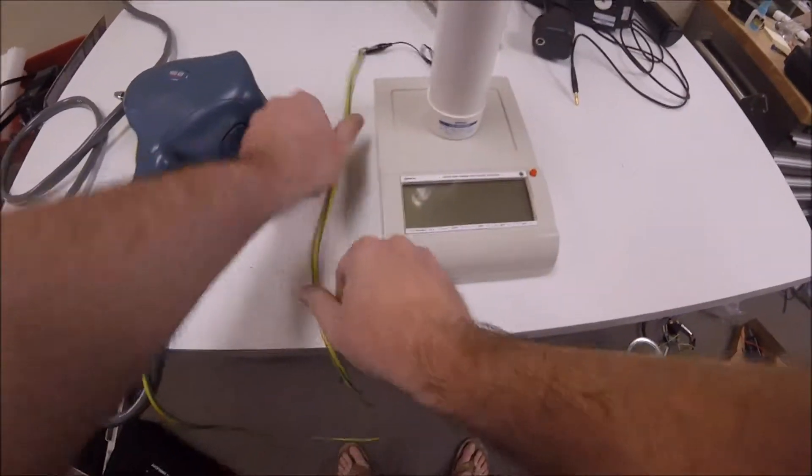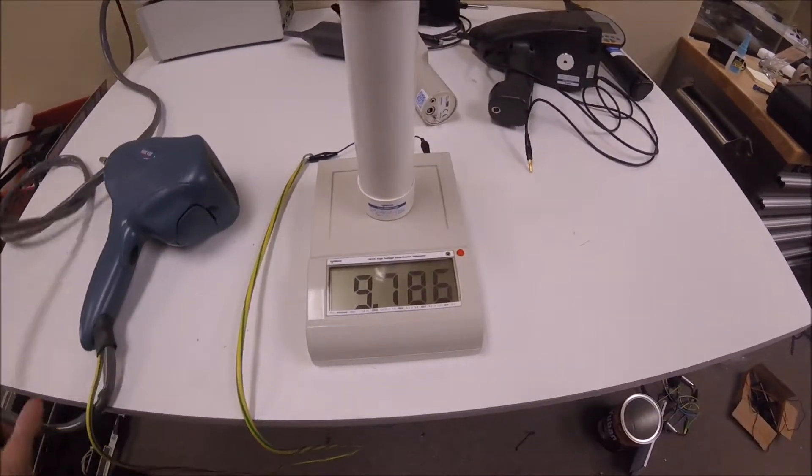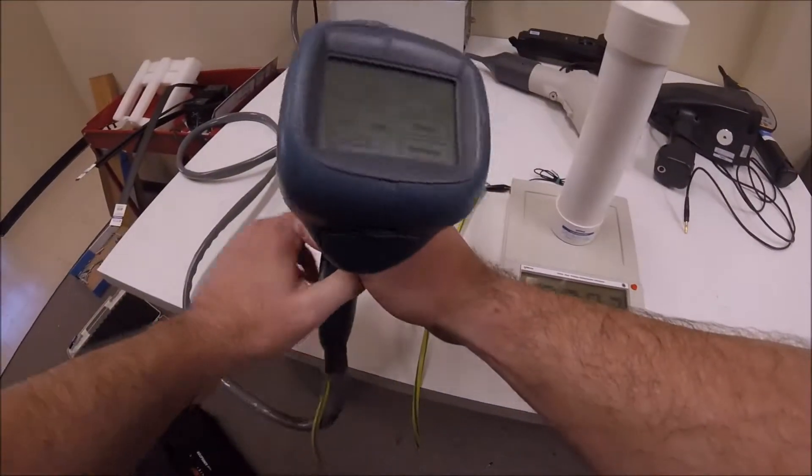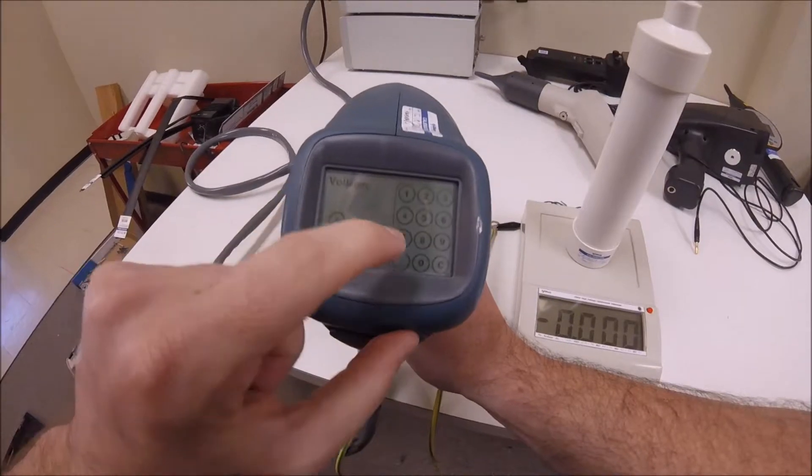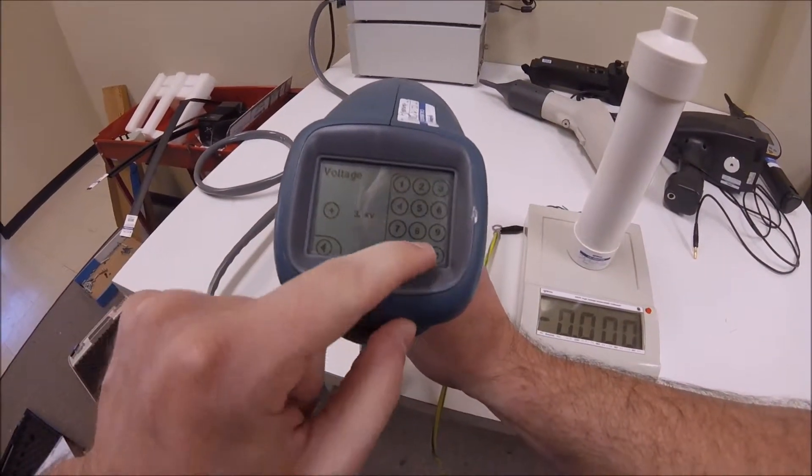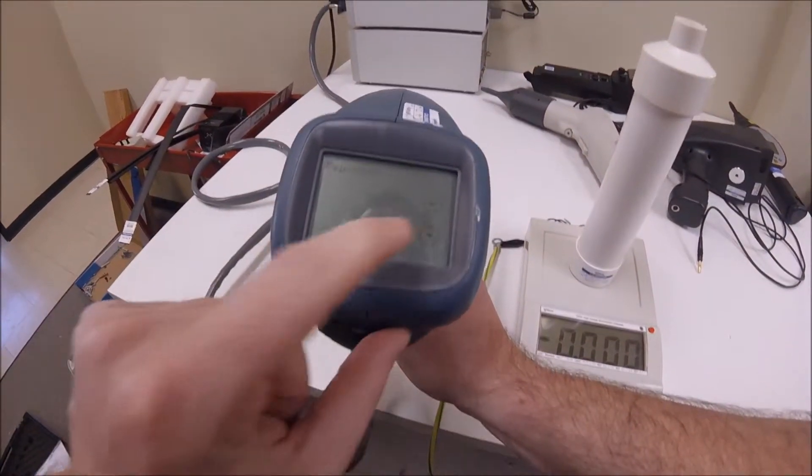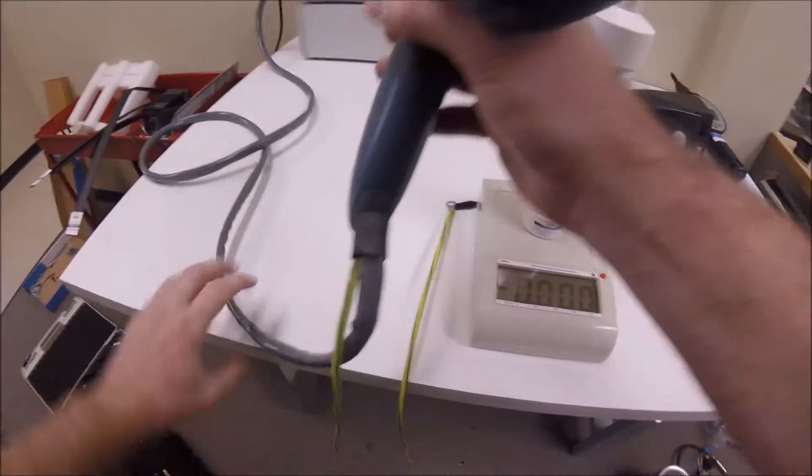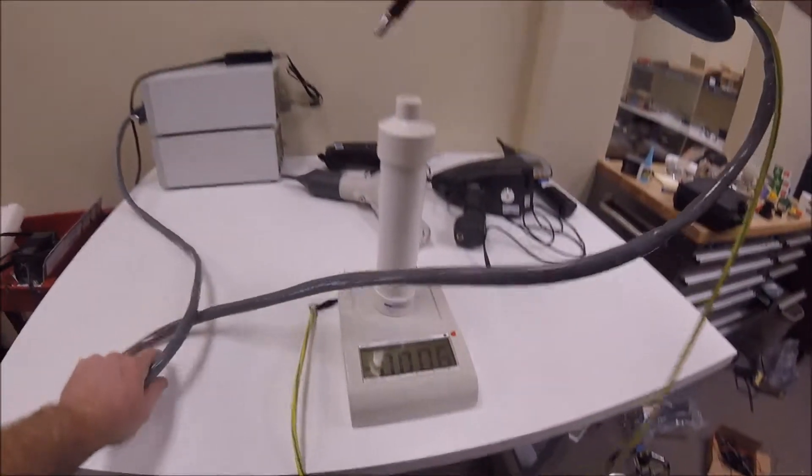Turning the voltmeter back around and using the one button in the top right corner, picking up our 438 and programming it to 30kV and set the frequency to 1Hz, which is the best speed to get stable results and coincides with the discharge intervals of IEC 61000-4-2 and other standards.